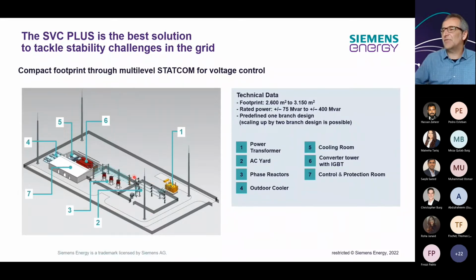The area here will be fenced off. There's an interlocking system so that you will not touch the live parts. The same thing is in the converter room, where we make sure you will not be able to enter the room if the whole system is live.